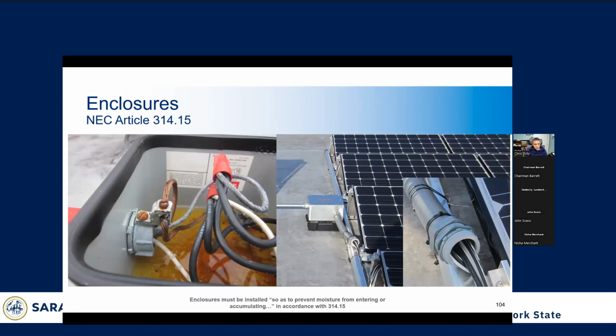Here we have an enclosure that's not only suffering from water buildup, as you can see in the bottom, but the lugs on the conduit are not rated for wet environment. You can see they're rusting, and eventually they're going to wear away and break off. The wire nut terminations also are not rated for the environment. This is a situation that would have been well served by the installation of a weep hole, like we just talked about in the previous slide, or the previous one before that.